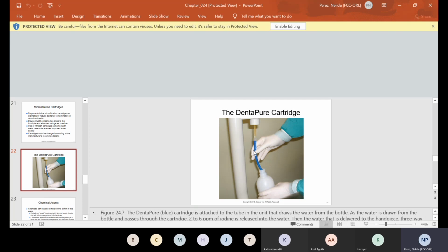Now, by the way, the hose is what gets that biofilm. So say, for instance, you're taking out the bottle and you're going to put new water in the bottle. Not only do you clean out the bottle, not only do you clean this part here where it gets screwed back into the unit, you also want to wipe down the hose and get that slime off the hose that goes inside the bottle, because after a while that also gets very slimy.